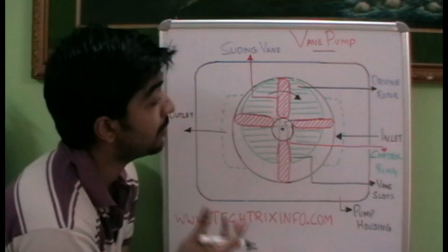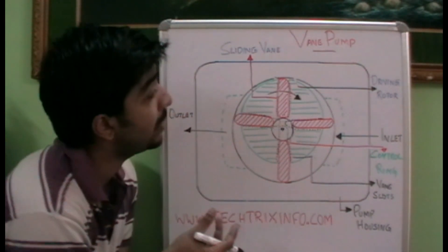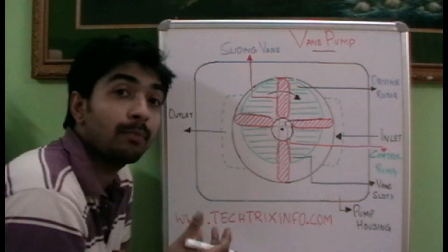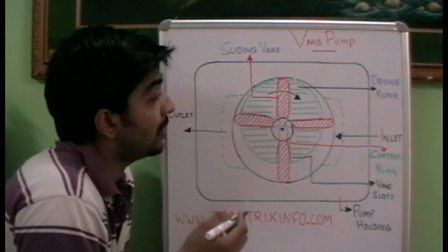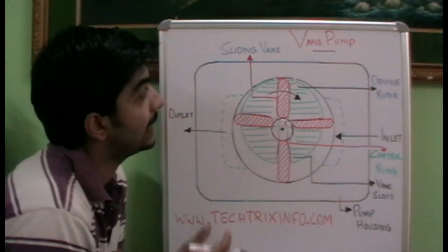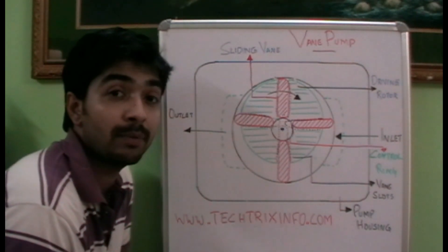That's how simply a vane pump works. And the advantage of the vane pump is that the vane pump is capable of giving a continuous flow compared to the pulsating flow of a gear pump, and I hope you understand the vane pump.